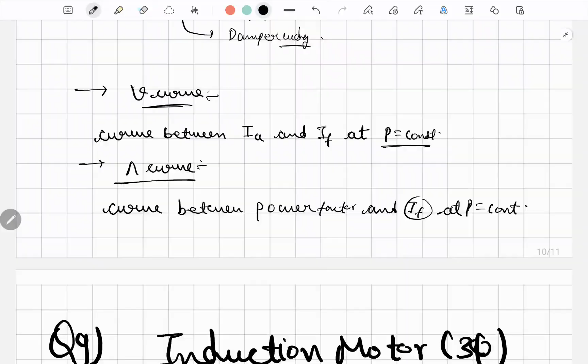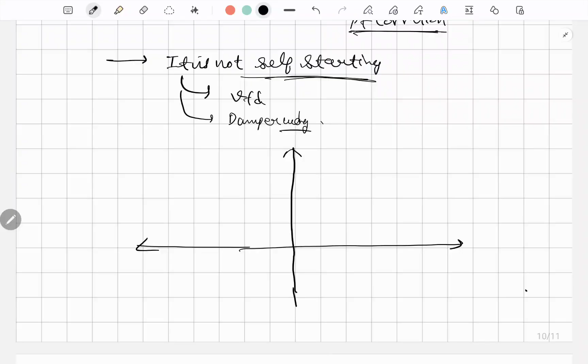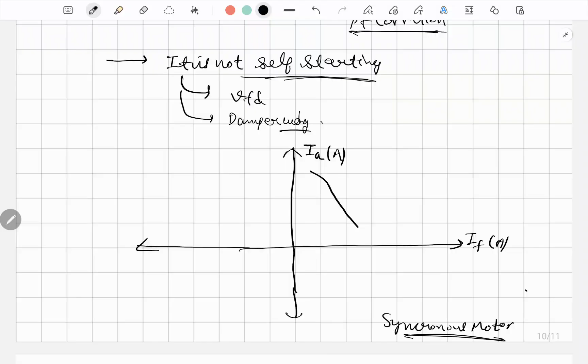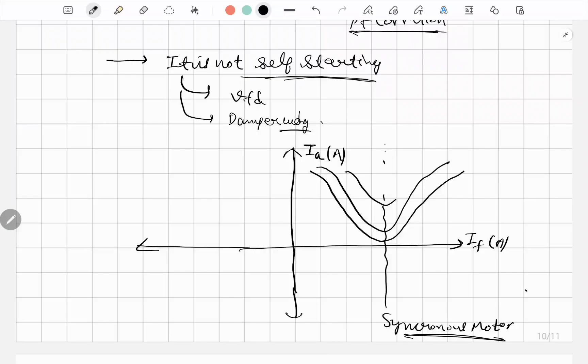Now let me draw this curve, the basic curve you need to know. Drawing the V curve first, for a synchronous motor: this axis is IA, this is IF, both in amperes. It looks something like this, and as we try to increase the load, the curve shifts upward - as the load increases, the curve gets higher. This dotted line is at unity power factor.